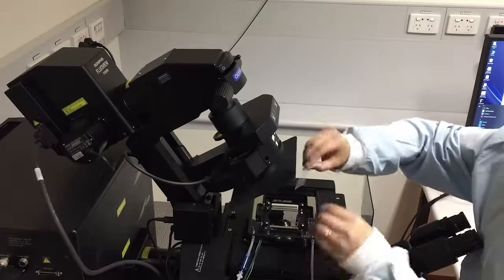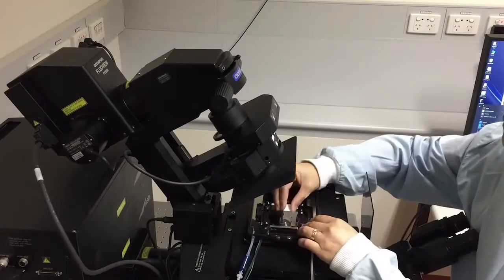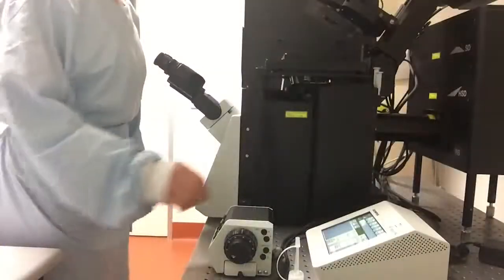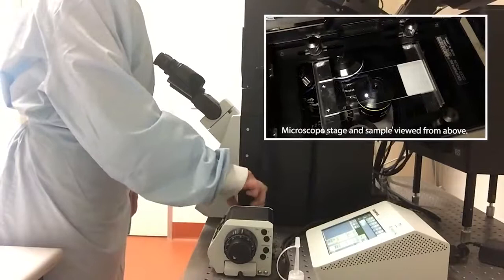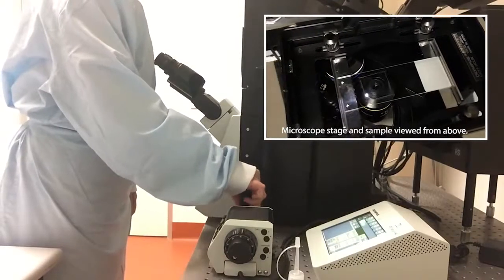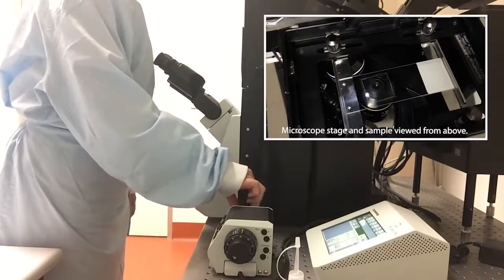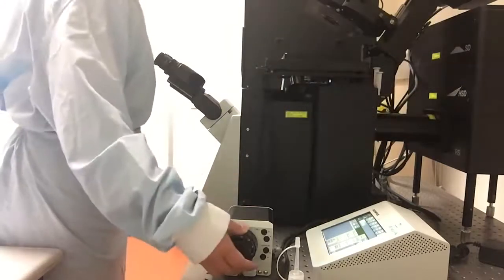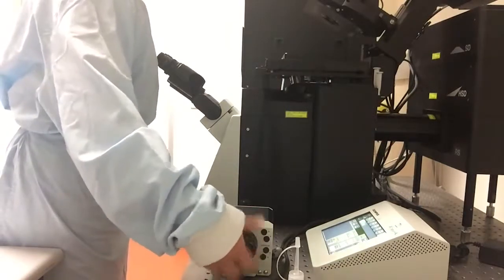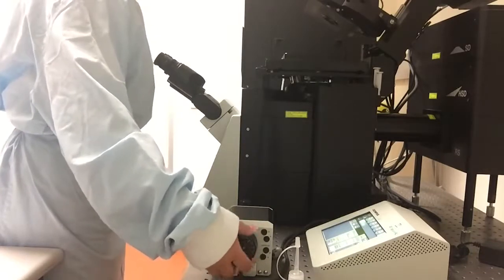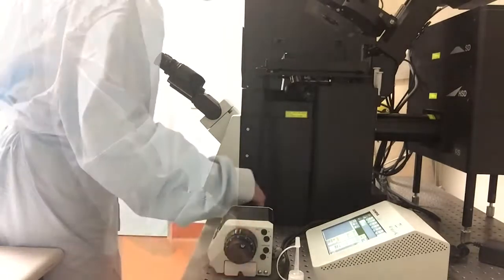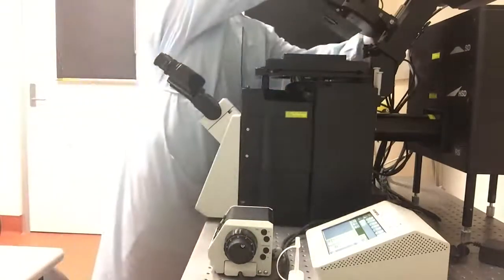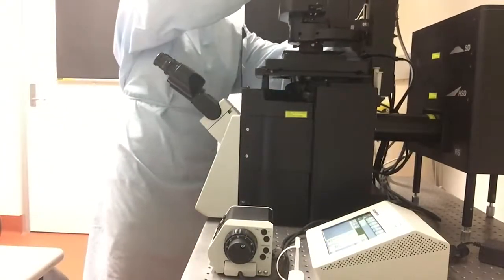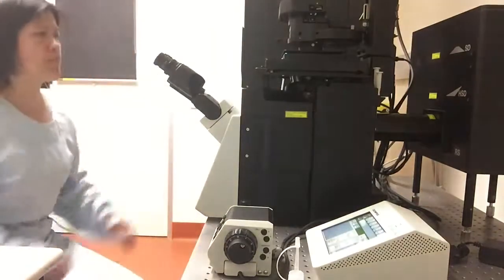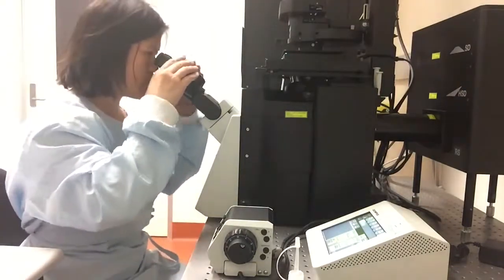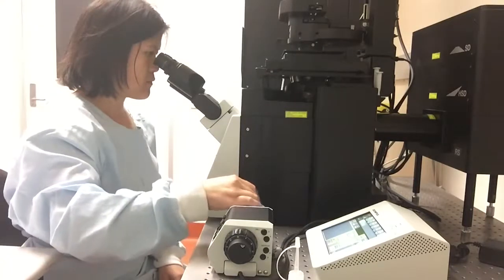Place your sample on the stage with the cover slip facing the objective. Use the wheels on the control panel to move the sample in X and Y to center the region of interest. You may need to raise or lower the objective using the focus wheel to get closer to the focal plane. Gently lower the upper part of the microscope back into its original configuration. Check your sample by looking down the eyepiece and adjust using fine focus.